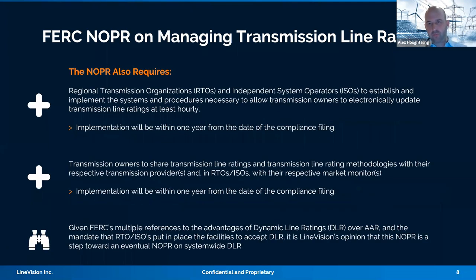In addition, and this is also signaling something crucial, RTOs and ISOs are going to be required to be able to ingest hourly data for advanced line ratings. Specifically, they're going to need to look at a 10-day rolling ambient adjusted rating updated hourly. So bottom line is 10 days times 24 hours, there will be 240 hours - 240 individual line ratings that will need to be updated on an hourly basis.